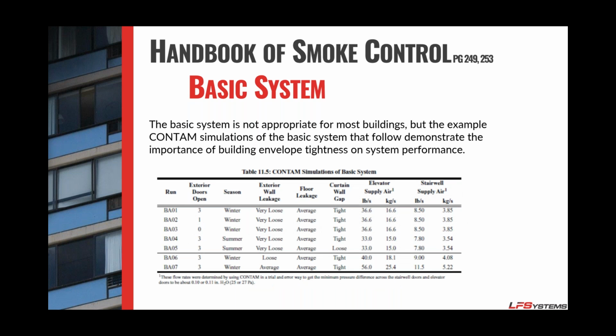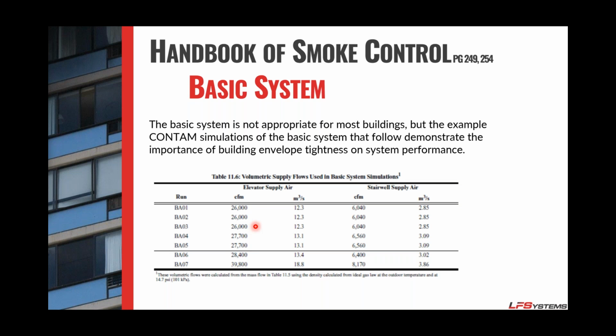If you look at the Contam example, you'll see where the system can work. If your construction has very loose exterior walls, this may work for you. The fan dumps a whole bunch of air into the shaft, but because there's so much leakage, it actually balances itself out. No matter how many doors are open, no matter what's happening, you basically maintain about the same amount of air. And again, the reason is that there's so much leakage that opening a door really doesn't change that.